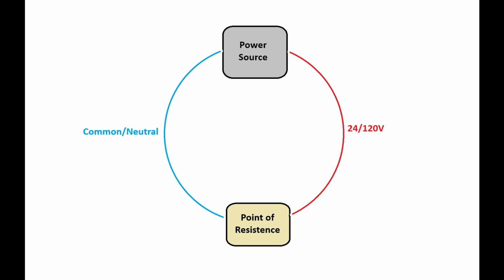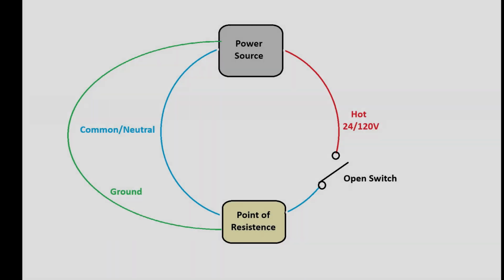Now, circuits are never really this simple. They always include some kind of control switching. They include ground wires. And so the number of reference points that we can use to get a reading will start to multiply. What also can happen is, depending on the position of these control switches, proper reference points can actually move around. So it's not so static. So let me show you what I mean by that.